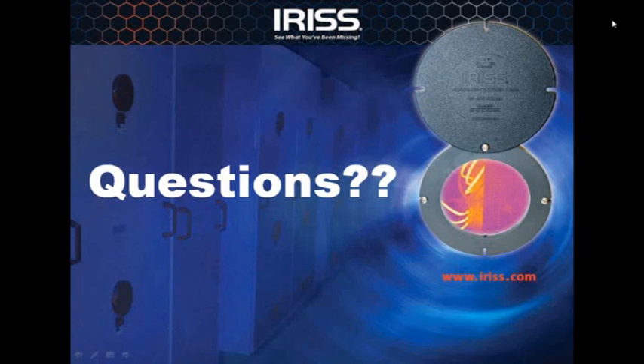And as I mentioned in the presentation, we have what we class as fixed and guarded condition. Now an infrared window really should have a lens. That lens should transmit infrared at a given rate so you can do your calculations. But opening and closing an infrared window shouldn't impede on anything on the high side of the switch, so you wouldn't trigger an arc flash explosion. Whereas if it was a grill, it's a vent. What I class it as, if the inside atmosphere can mix with the outside atmosphere, that's not a window, that's a vent or a port. Now, obviously for ultrasound, I can't ultrasound through a solid.